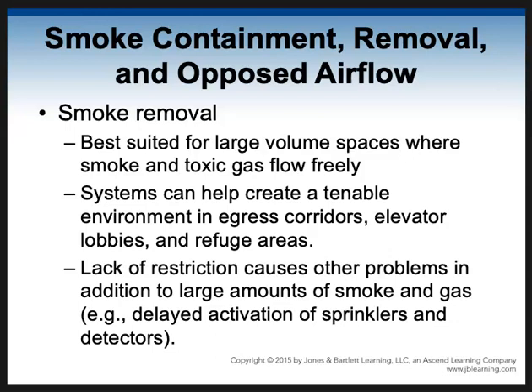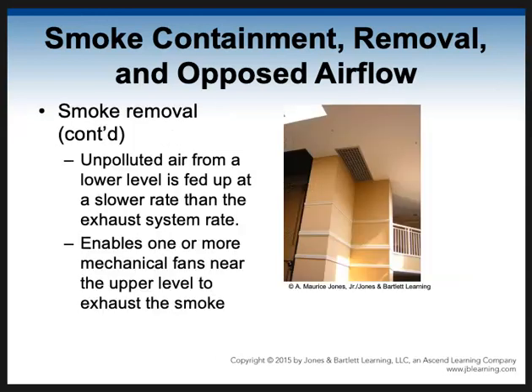Now, lack of restriction causes other problems in addition to large amounts of smoke gas. So if they have delayed activation of sprinklers or detectors, this can be a little bit of an issue. Unpolluted air from a lower level is pulled up at a slower rate than the exhaust system rate. So they're going to feed the air in, because if they push too much air in, they're going to encourage the fire to grow. But they want to have fresh air coming in below and then really big fans pulling air out above. So the mechanical fans near the upper level are going to exhaust the smoke out.